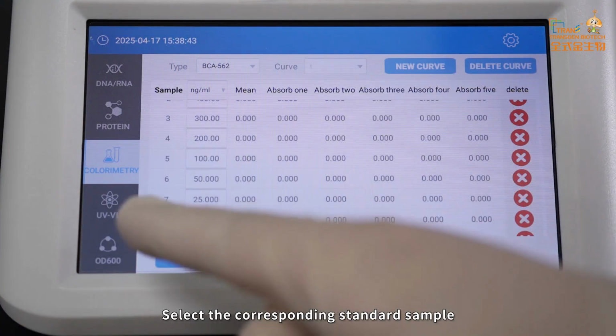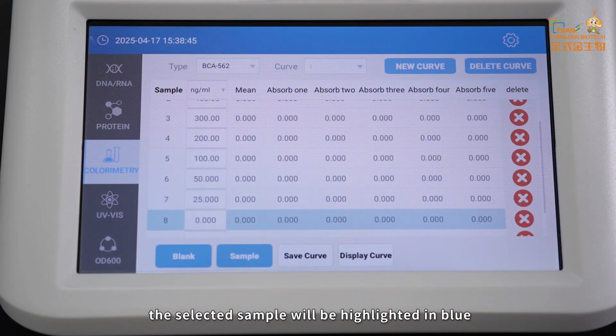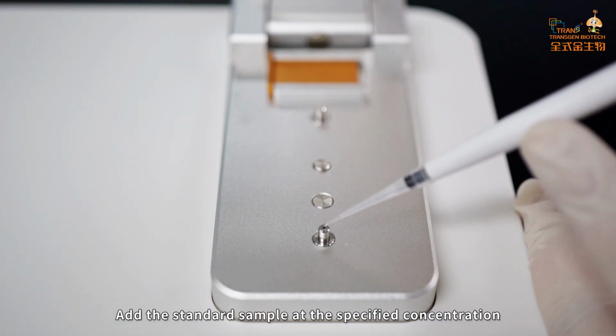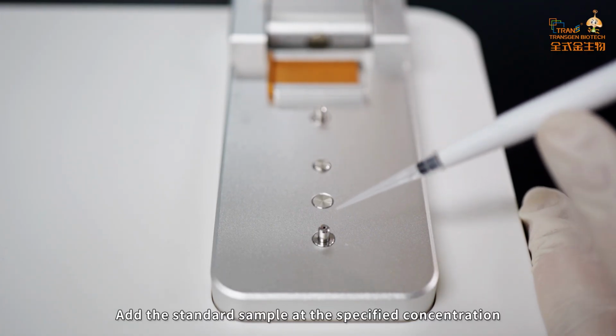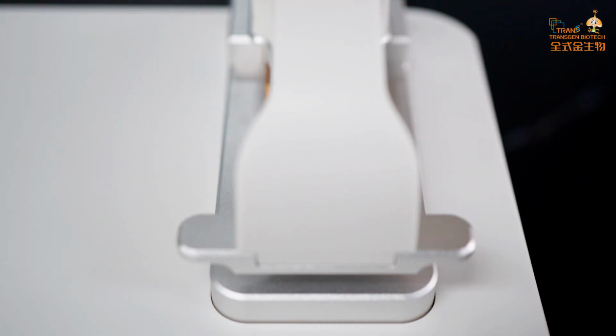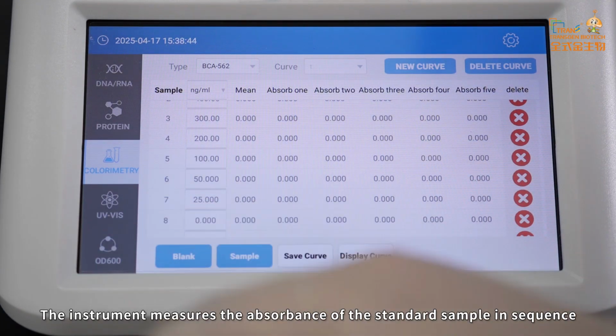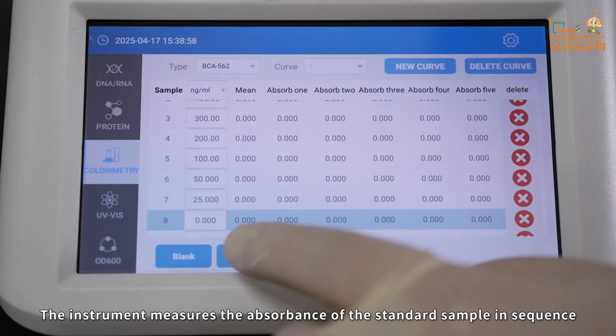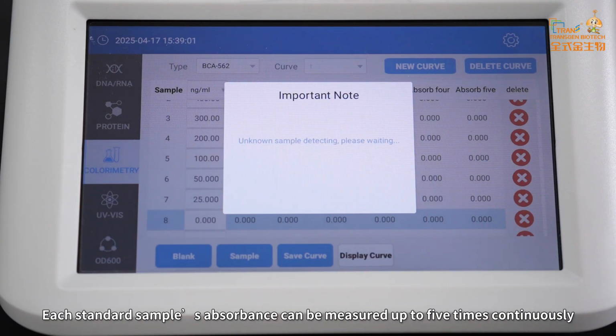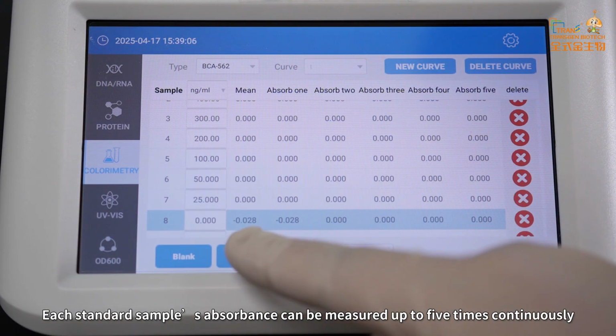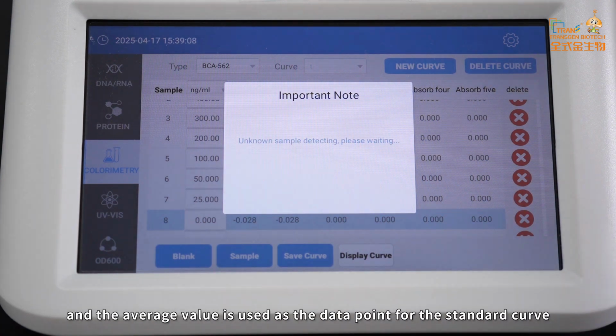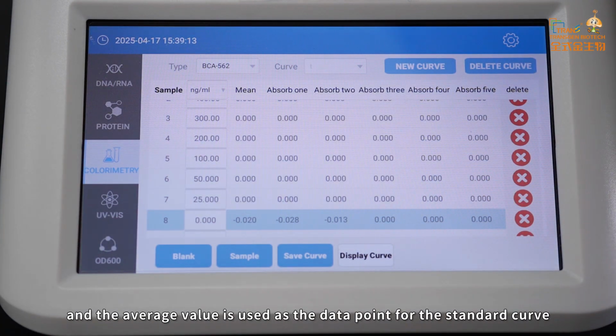Select the corresponding standard sample. The selected sample will be highlighted in blue. Add the standard sample at the specified concentration. The instrument measures the absorbance of the standard sample in sequence. Each standard sample's absorbance can be measured up to 5 times continuously, and the average value is used as the data point for the standard curve.